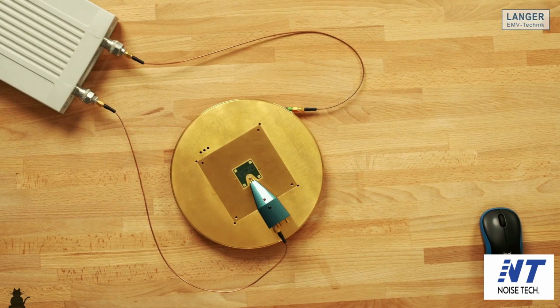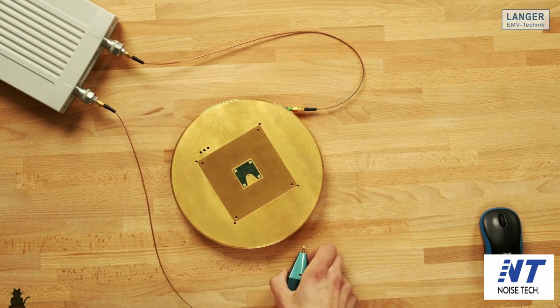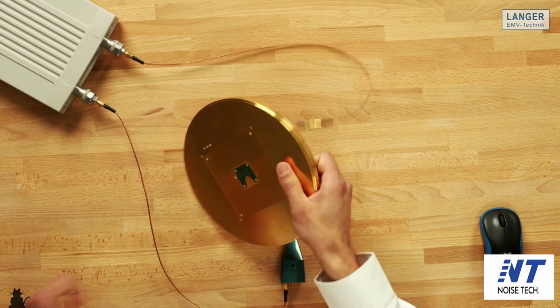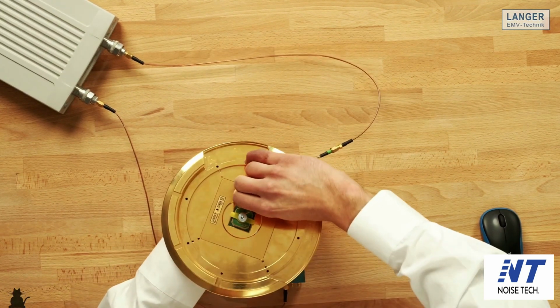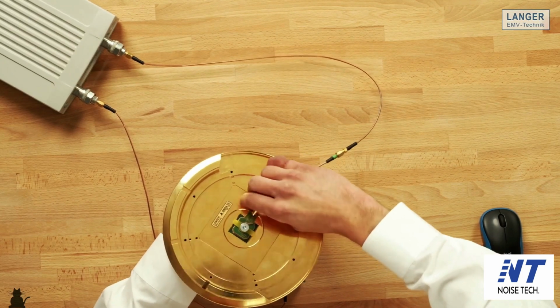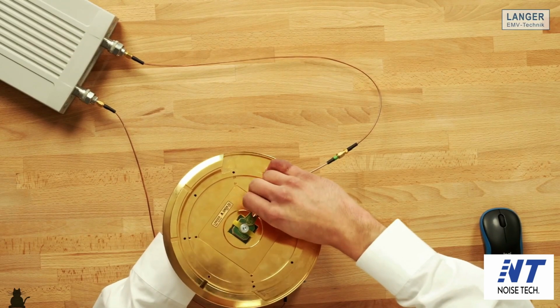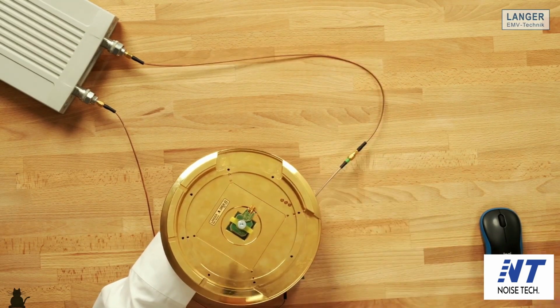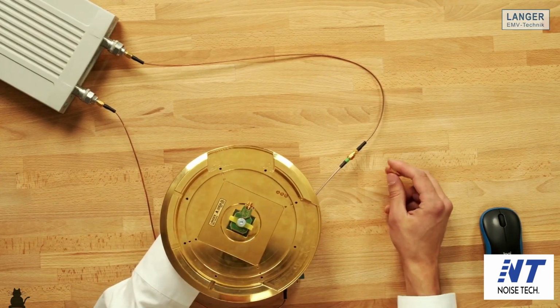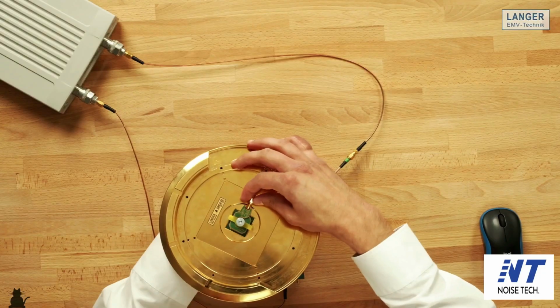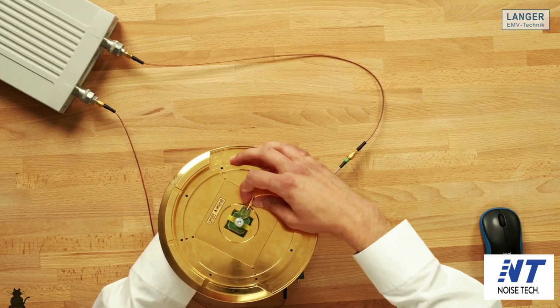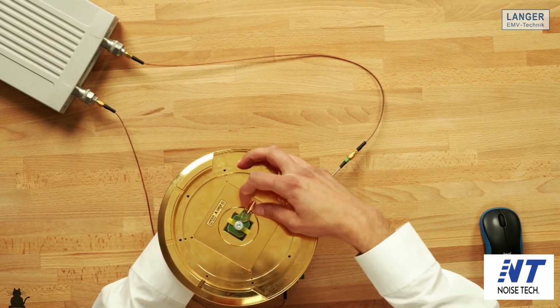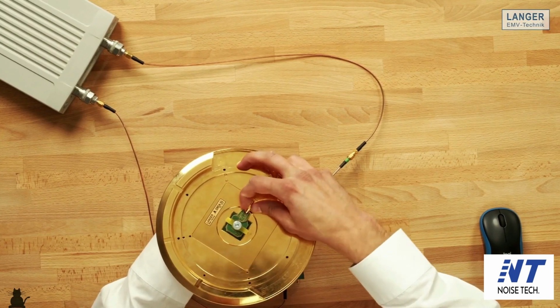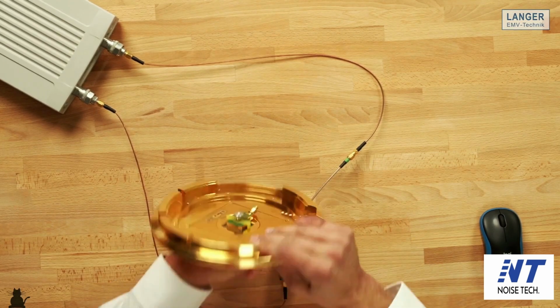For this, I disconnect the supply of the probe again. I remove the probe from the ground plane. Now I also remove the SMA cable from the calibration hardware, from the DLM A01. What is important now, when calibrating the ampere meter and the voltmeter of the P500, is that we need to put the 50 ohm terminating resistor on the bottom of the feed-through standard here. This is done.